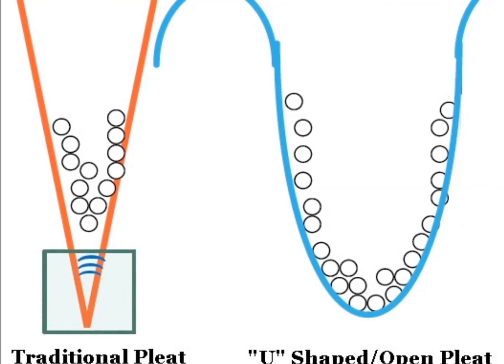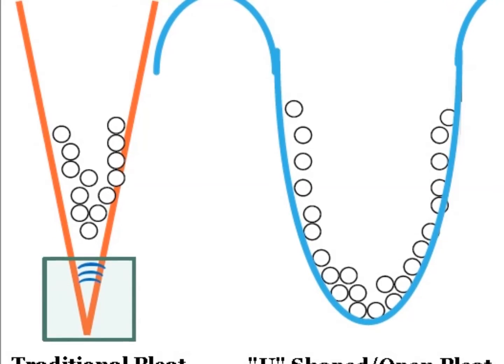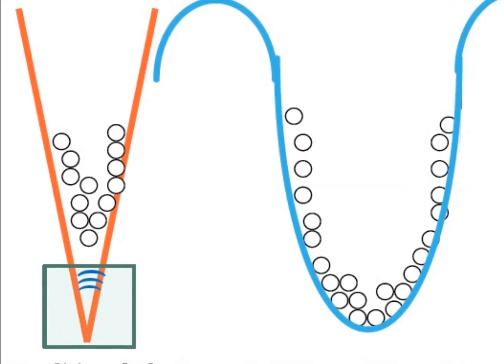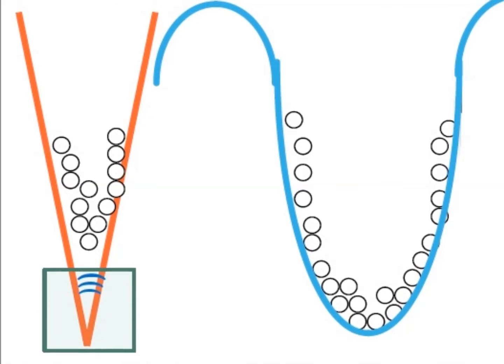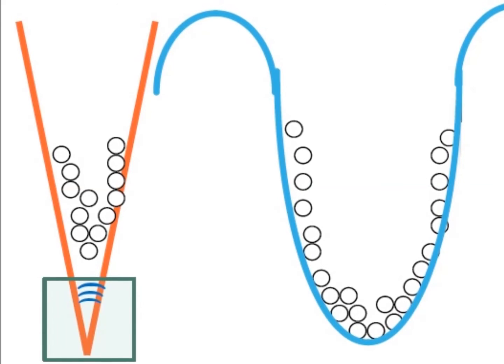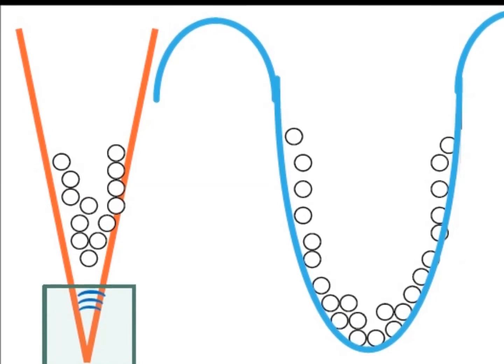How the pleats themselves are configured is also an important indicator of the filter's performance. Traditional V or chevron style pleats are the dominant configuration. With such sharp changes of direction, voids are left that pinch off airflow and filtration capacity, leading to shorter filter life and more energy use over time. Pleats with a U-shaped configuration allow for full utilization of the media area, resulting in longer filter life and lower required fan speeds.